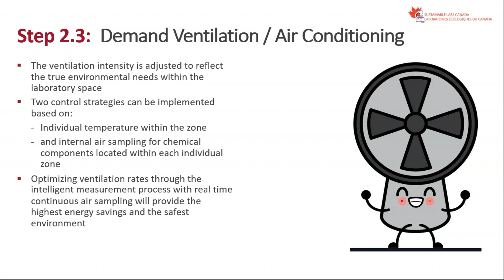And for instance, if you are in a situation at night when no people are present, you can slow down the system and bring it to as low as 4 air changes per hour or even lower. In some instances, you can go down to 2 air changes per hour and provide substantial savings from the ventilation requirement.